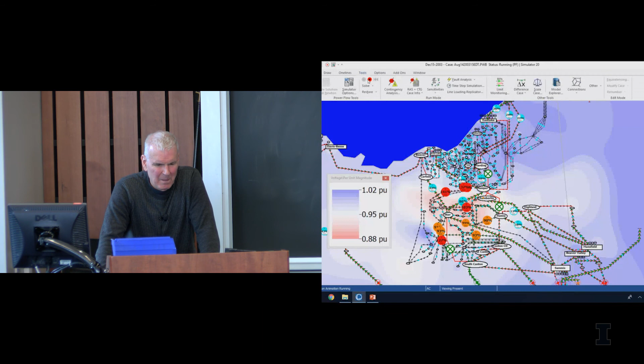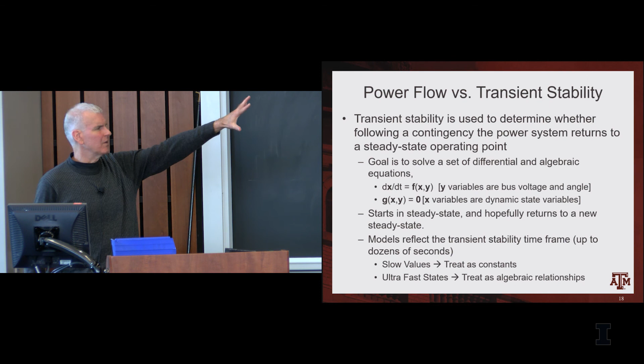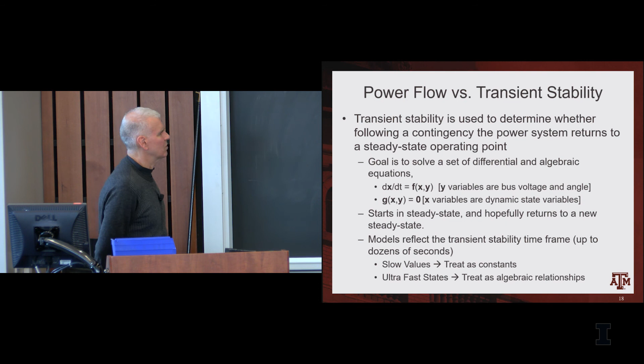As we get to the part where the grid fails, you start getting dynamics going on. And the grid starts oscillating around. It's no longer in what we call a quasi-steady state condition. And this is something that we study in power system dynamics. We start talking about differential equations coupled with algebraic equations. Now we move from a modeling time frame of perhaps minutes out to dozens of minutes to a time frame of seconds to less than a second, maybe on the order of one cycle, which would be a 60th of a second.